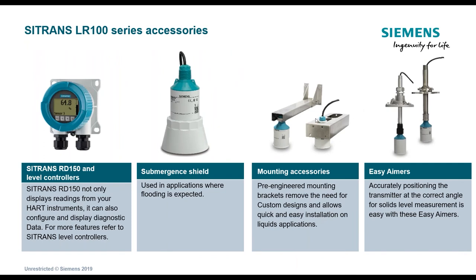Looking at the portfolio and accessories: some customers might want to see the level remotely on a display. To that end, we have the SITRANS RD — Remote Display 150. This is a two-wire loop-powered device that you wire between the transmitter and your control system, allowing you to graphically see what the transmitter is outputting. This is a HART multi-drop device, meaning you can wire up to four transmitters into this one device.